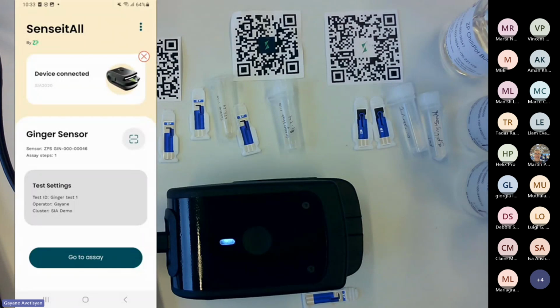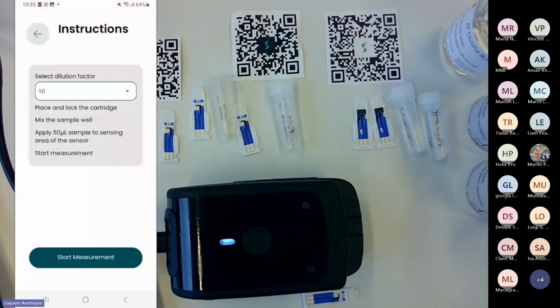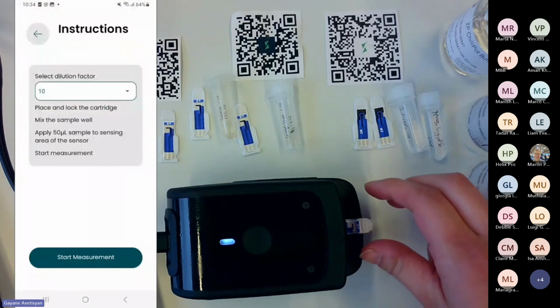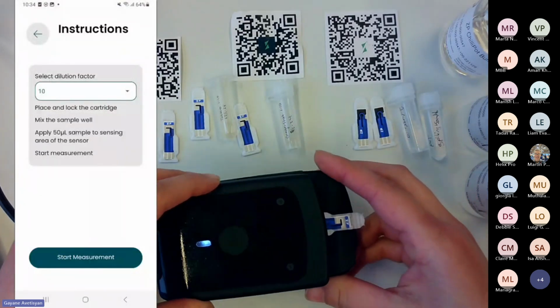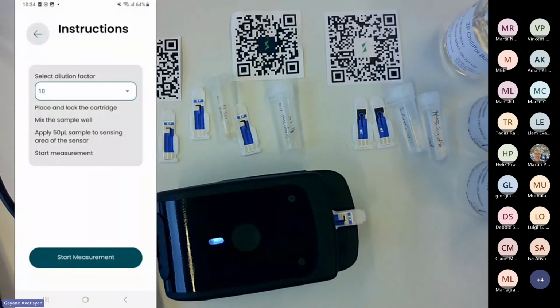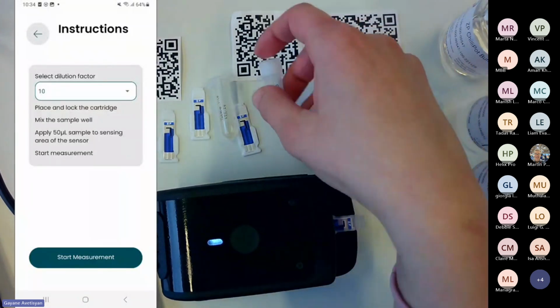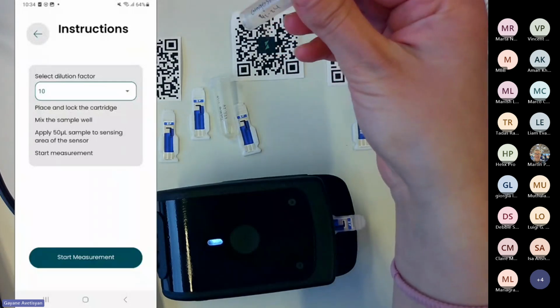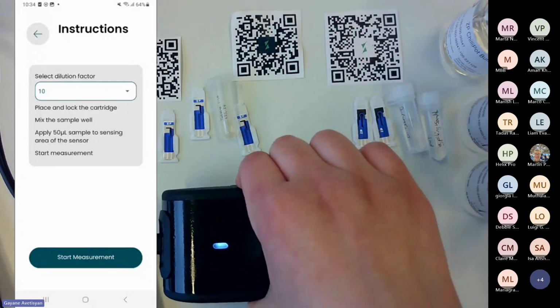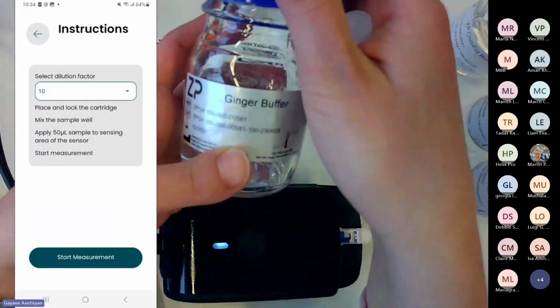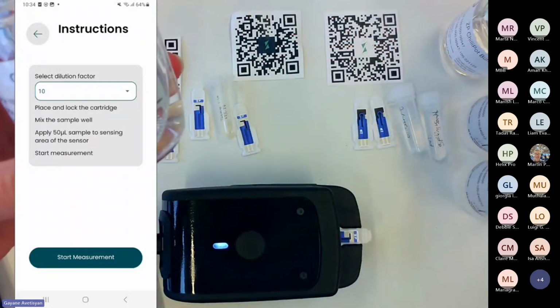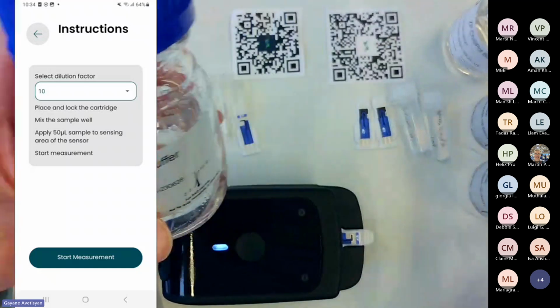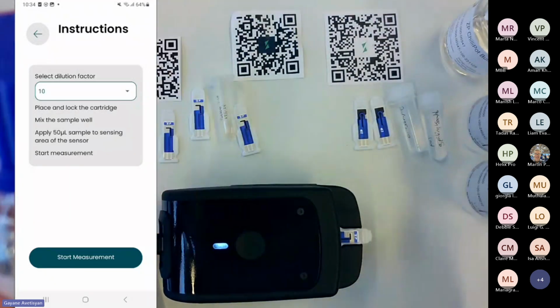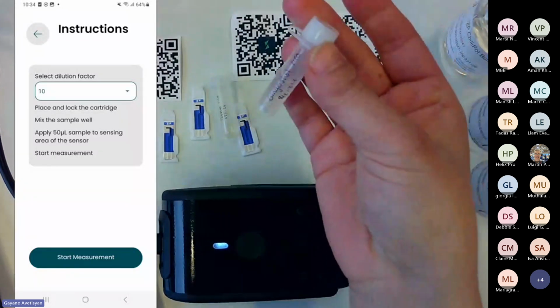I will press go to assay, and I will get the instructions. And this instruction screen will be different for each analyte. So right now we are doing it for Ginger. So I will place the Ginger sensor and lock the cartridge, click the movable part up to connect the sensor. And I will show the solution that I have today. The Ginger assay comes with the Ginger buffer. And the sample that I wanted to test was the ginger shot solution. So I mixed the ginger shot solution with the ginger buffer at a 1:10 ratio. And now I have this solution that I want to test.